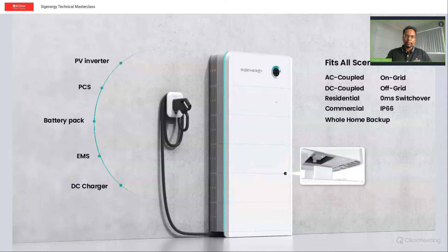It's IP66 rated, so the inverter and batteries are fine outdoors - we'd recommend a little bit of shade, just not direct sunlight, because it is lithium iron phosphate. It can do whole home backup, true 3-phase unbalanced whole home backup, and single-phase whole home backup with 0 millisecond load side disruption. There's a patented algorithm - I'm happy to share that Gateway document on how we achieve that. It doesn't go into extreme detail, but gives an overview.